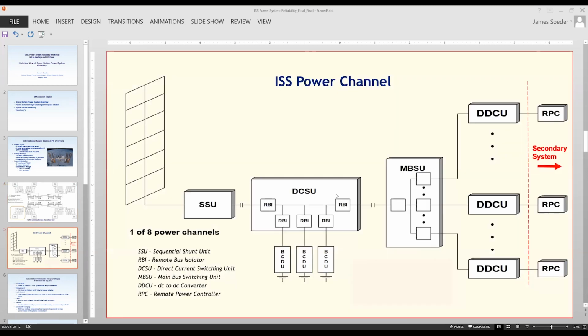This is a quick schematic of what a channel looks like. You've got a solar array, a regulator, a switching unit which allows you to bring on the paralleled battery charge/discharge regulators, and that goes through the primary switching network shown here. It feeds a set of DC to DC converter units, and the output of those units is, in fact, the secondary system. If you want to parallel power from another power channel, you have to parallel the DDCUs into the secondary in order to make that happen.